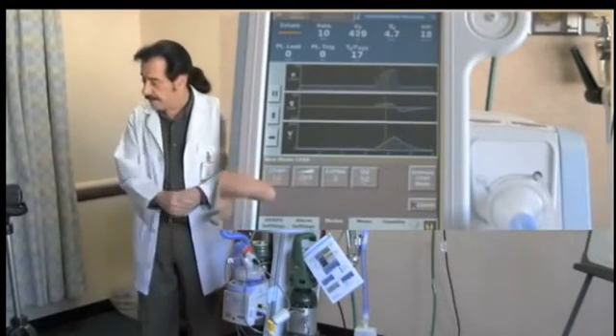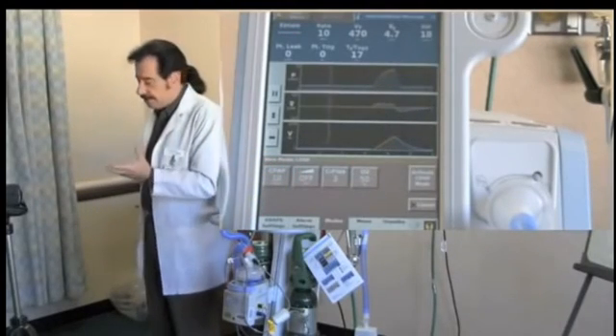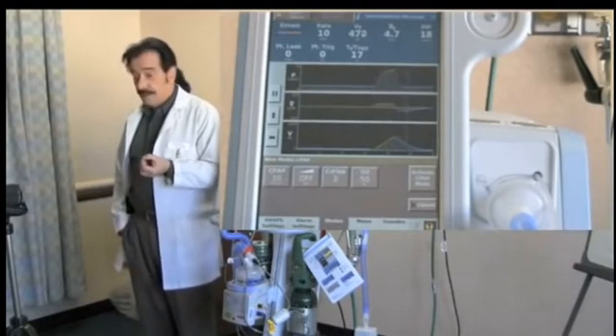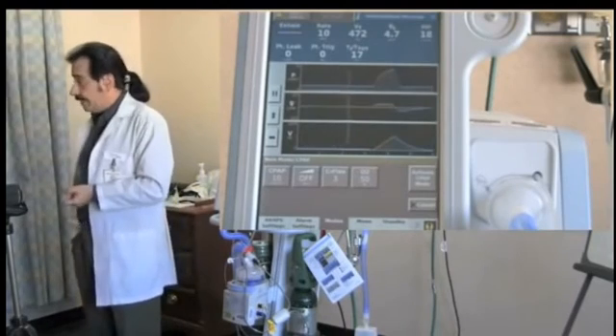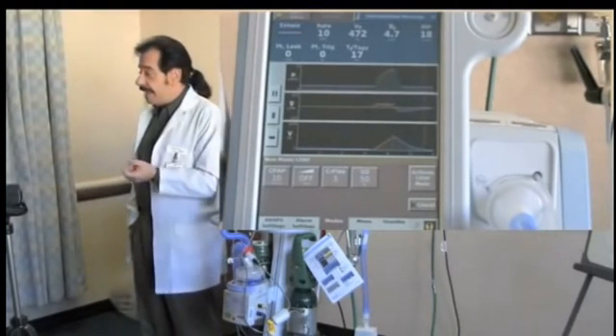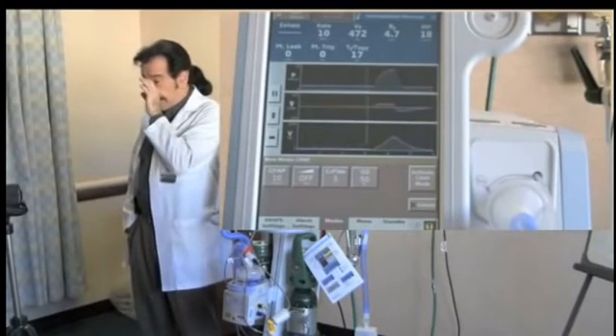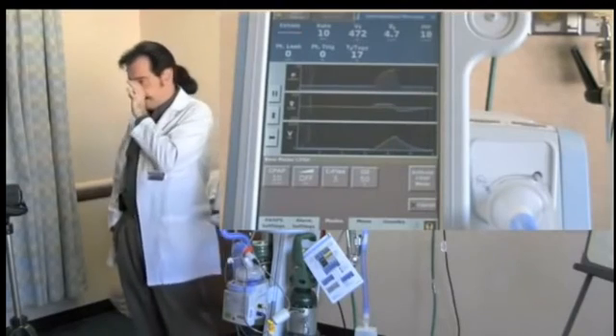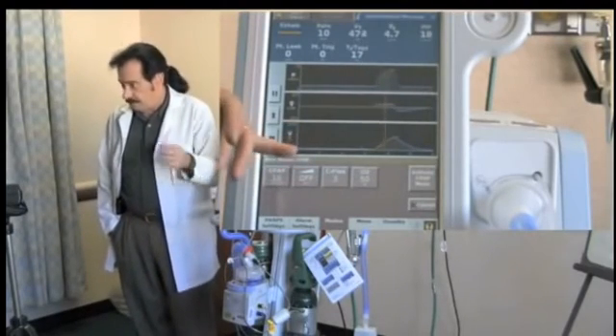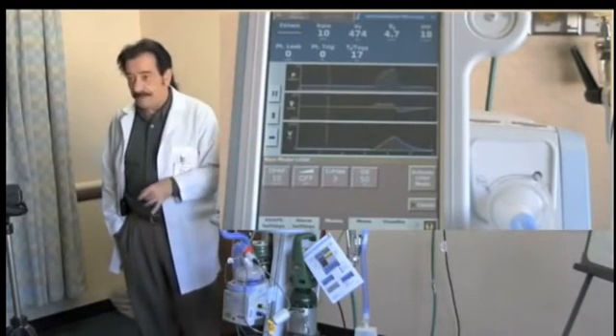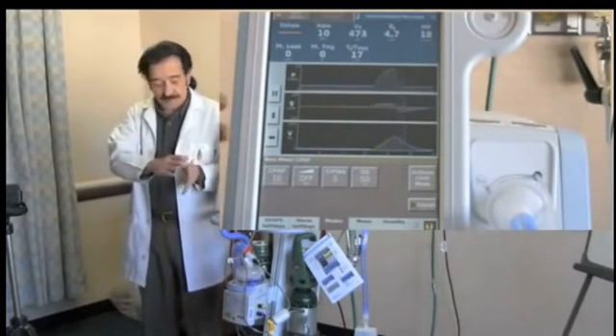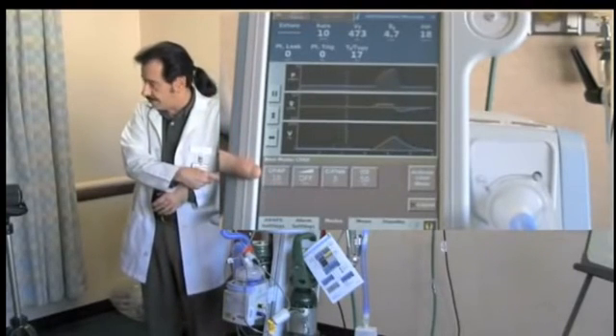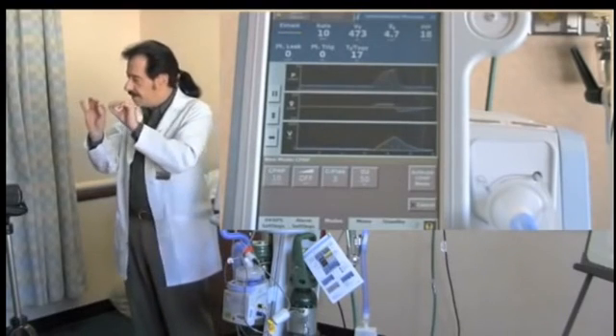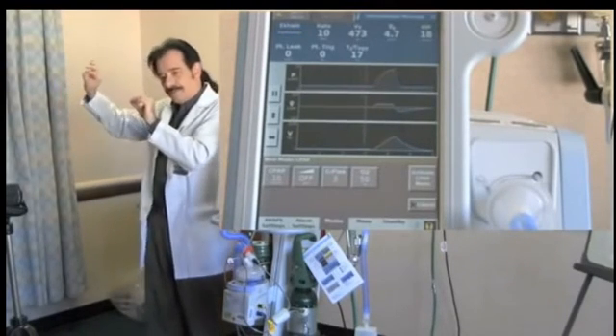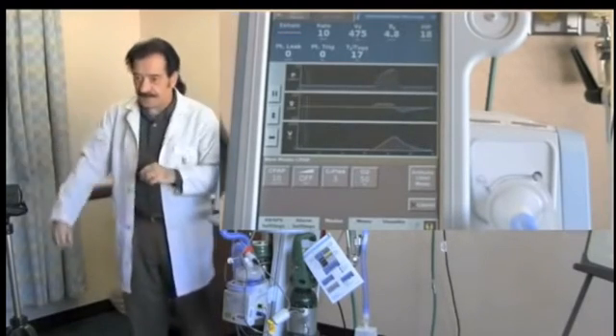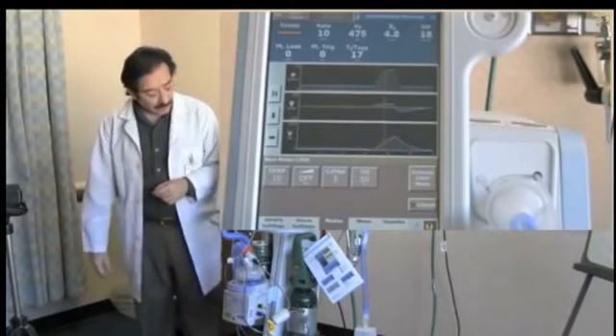You have a ramp on here. Now the ramp, a lot of times patients that are using rather high levels of CPAP to mechanically stent open their airways to prevent obstructive sleep apnea when they go to sleep may complain of that flow blowing in through the nasal appliance. Okay, I can't go to sleep with this blowing. So you can set the ramp for off, which means instantaneous, or from 1 to 45 minutes on this ventilator. So if you have it set at 45, it'll take 45 minutes for the machine to actually reach the 10 centimeters of water pressure. So it starts off at 0 for a few minutes, then it goes up to 1, it stays there for a little while, then it goes up to 2, and it just very slowly ramps its way up to the set CPAP level. Okay? We very rarely use that in the hospital.